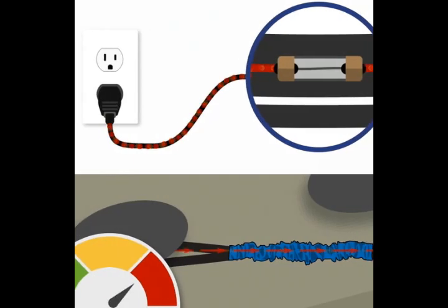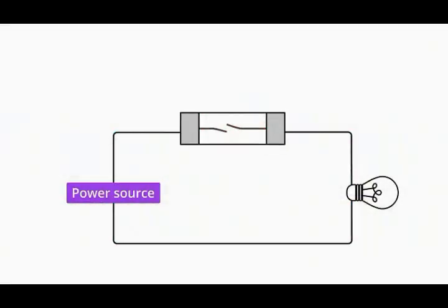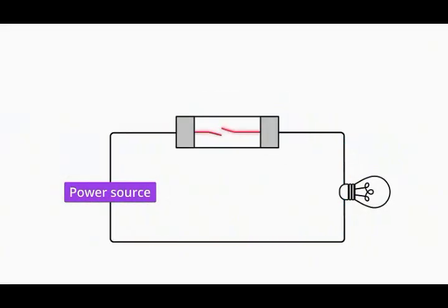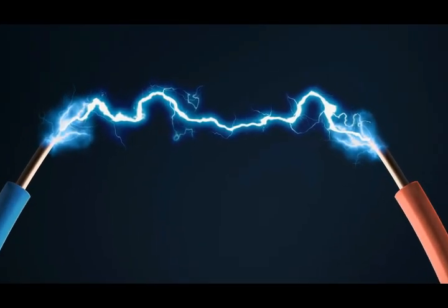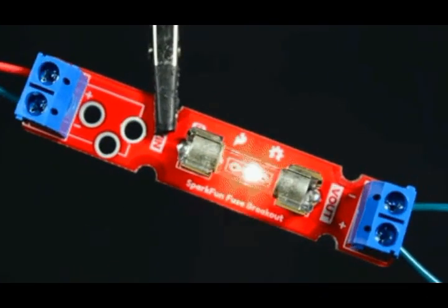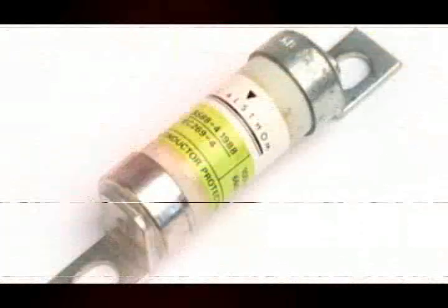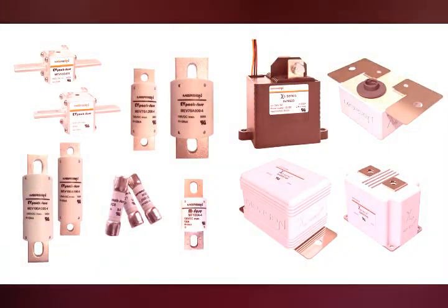Circuit breaking is difficult because the power supply of DC fuses has a constant voltage and is above 0 volts, so there is a possibility of arcing between the melted wires. In constant current circuits, after melting the metal wire, the available heat causes an arc and the stability of the DC current makes the arc not easily destroyed. To eliminate this arc, DC fuses are usually produced in large sizes to increase the distance between the electrodes and eliminate this arc.